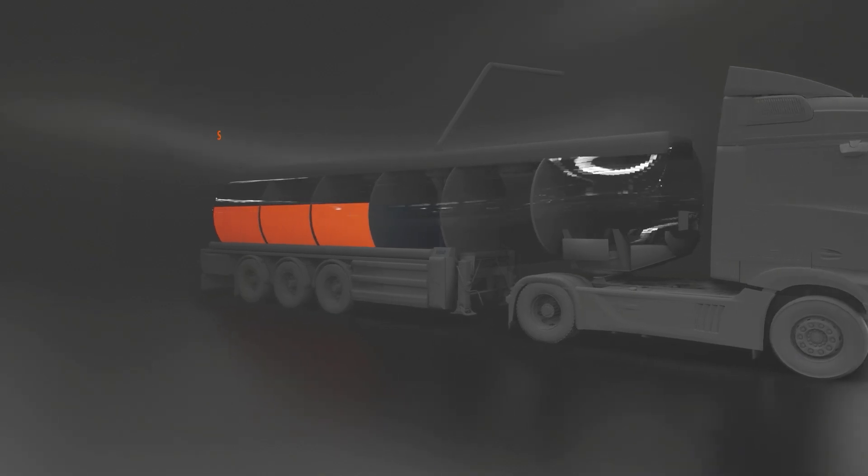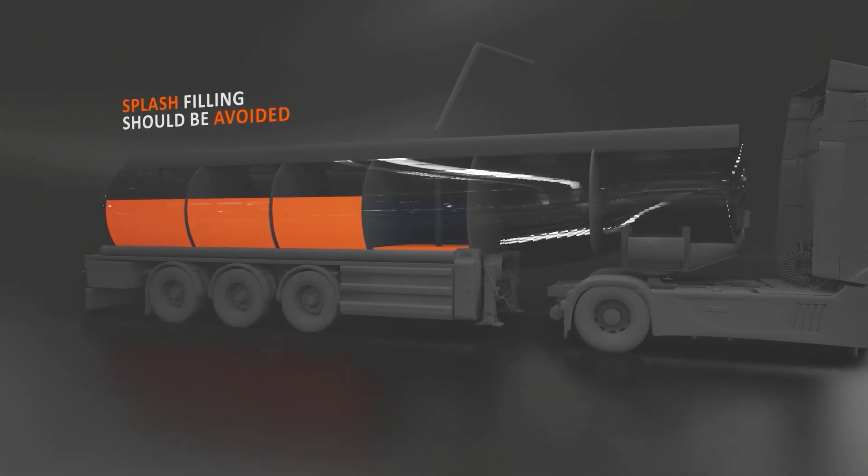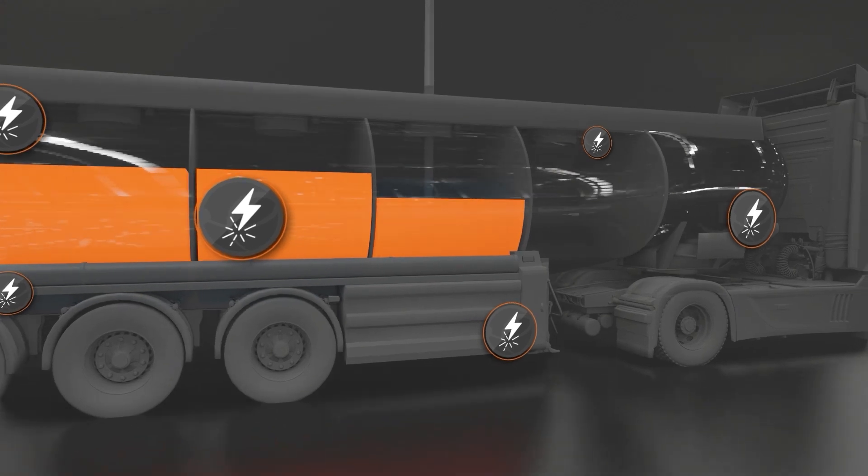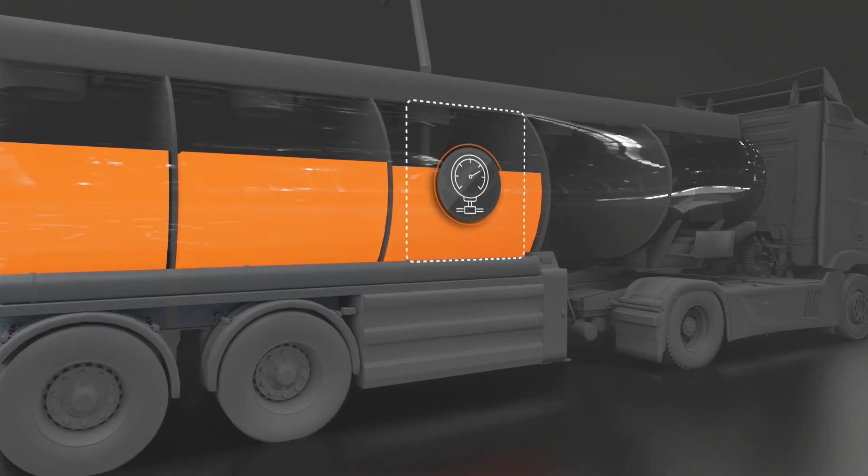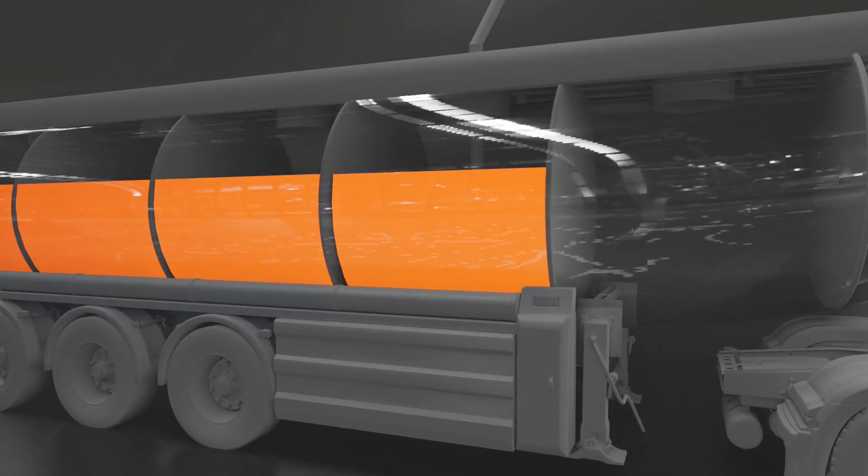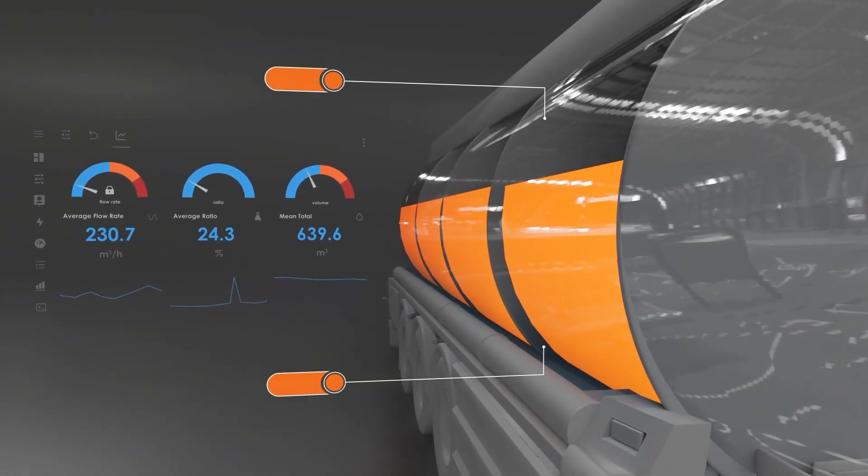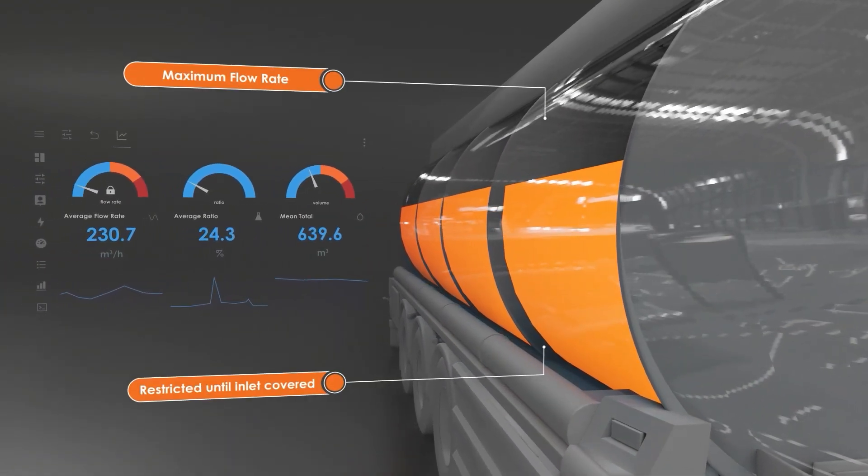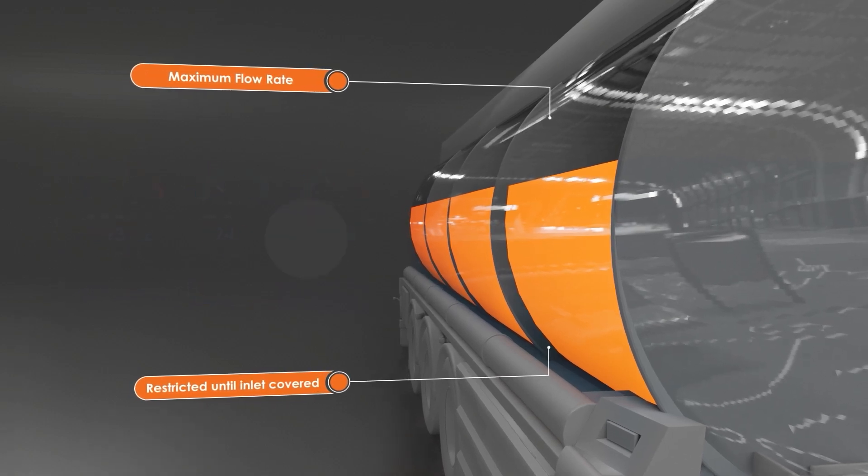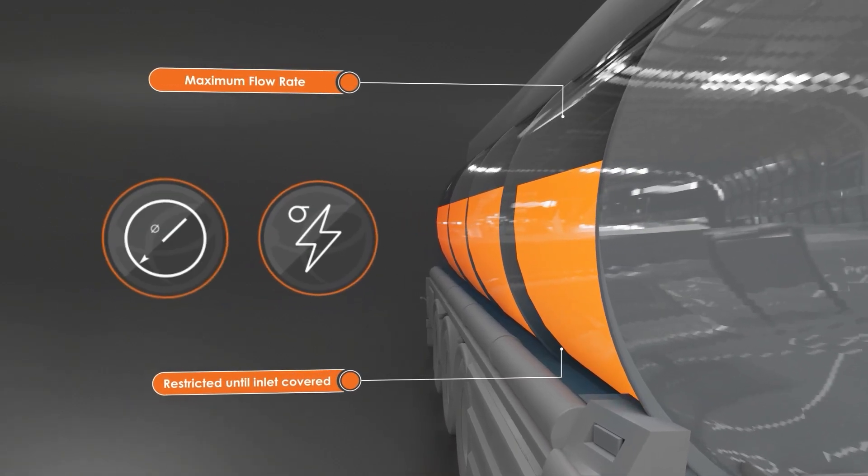Irrespective of the product, splash filling should be avoided as this increases the possibility of generating static. Flow rates are extremely important in minimizing the build-up of electrostatic charge. Initial flow rate should be restricted until the filling nozzle or inlet has been covered. The maximum flow rate should also be observed. These are dependent on factors such as the conductivity of the product and the diameter of the fill pipe.